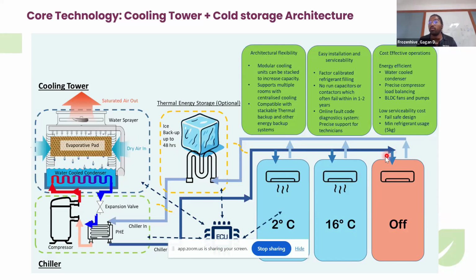If you can see here, there are three rooms shown. Let's say one room you want to keep closed since there's not much material available, and another room you're maintaining at 16 degrees for a ripening event, since banana ripening is usually done at around 20 degrees. You also have fruits like apples which you want to store at 0 degrees. It's perfectly possible with one single unit—you can maintain this room at 2 and this room at 16, and also turn off the rooms not in use. That's the beauty of this architecture.